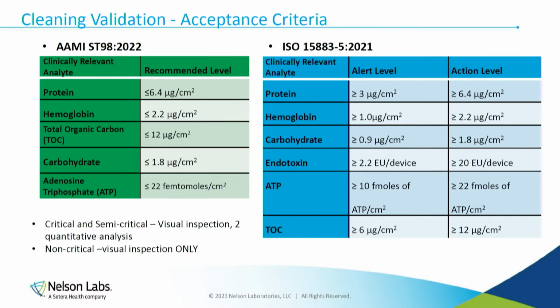Now, these are cleaning validation acceptance criteria, and you will see that ST98 has one, ISO 15883-5 has one. Now, keep in mind, FDA does not recognize the 15883 standards, the whole series. So this is for Europe. Okay, so they have action and alert levels. What they mean, we don't know. ISO doesn't specify it. That is something that we need to interpret. But what I'm starting to see is the alert level is now their action level, right? So they're more stringent on what these validations should be than the FDA is, right?